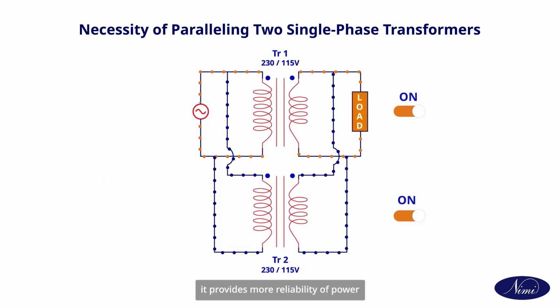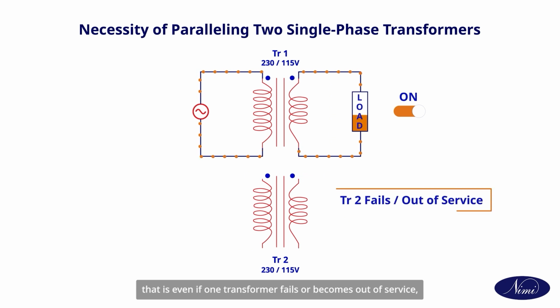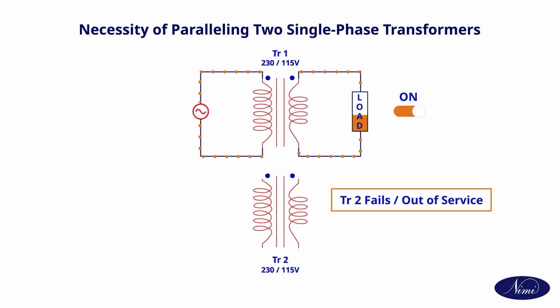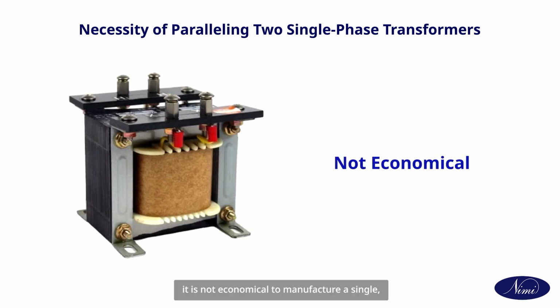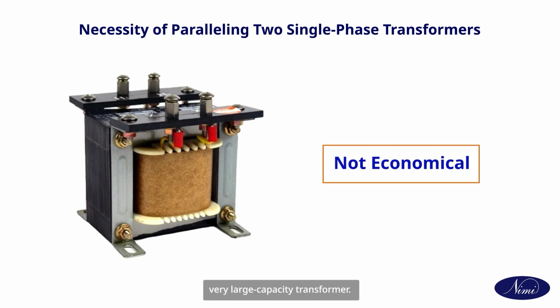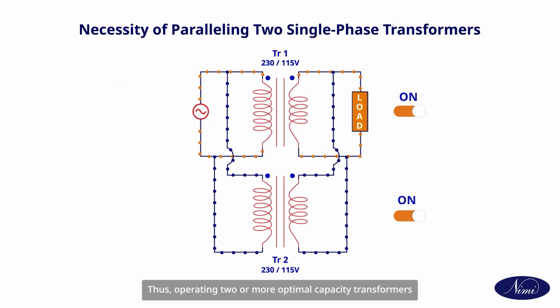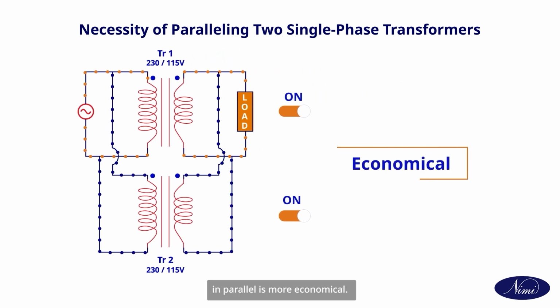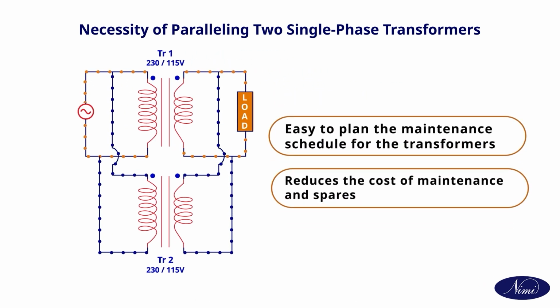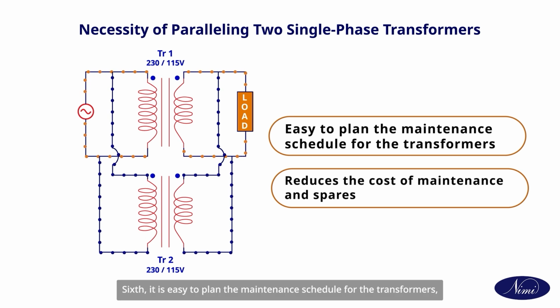Fourth, it provides more reliability of power, that is, even if one transformer fails or becomes out of service, other transformers will supply a certain amount of load. Fifth, it is not economical to manufacture a single very large capacity transformer. Thus, operating two or more optimal capacity transformers in parallel is more economical. Sixth, it is easy to plan the maintenance schedule for the transformers, which reduces the cost of maintenance and spares.